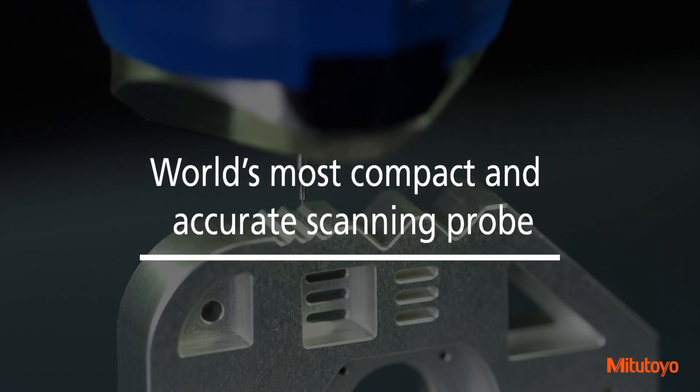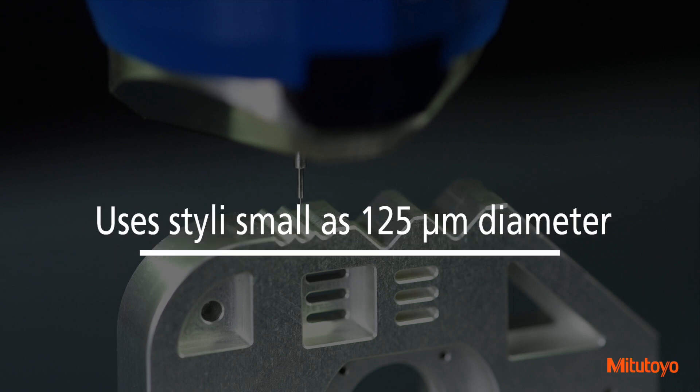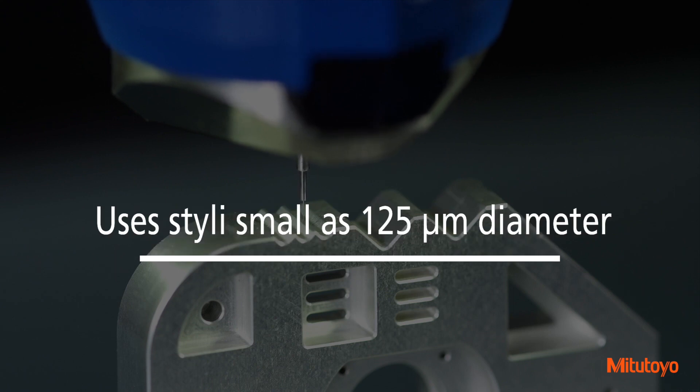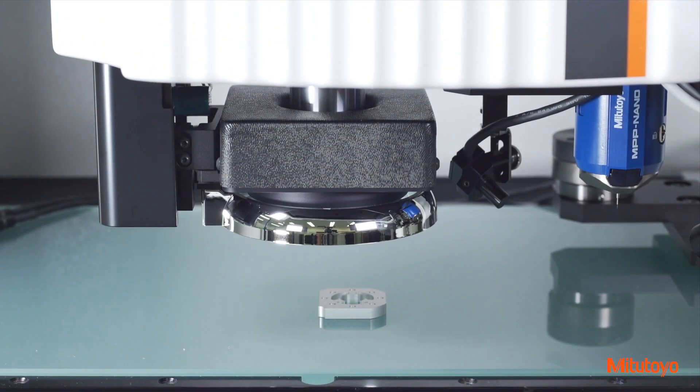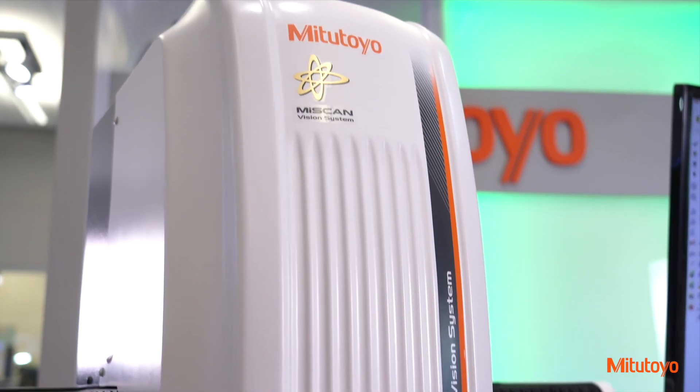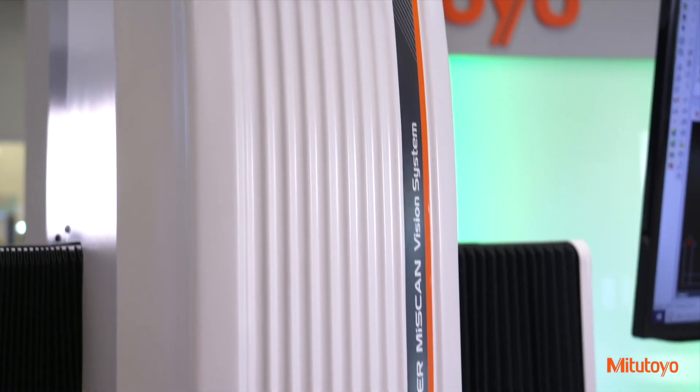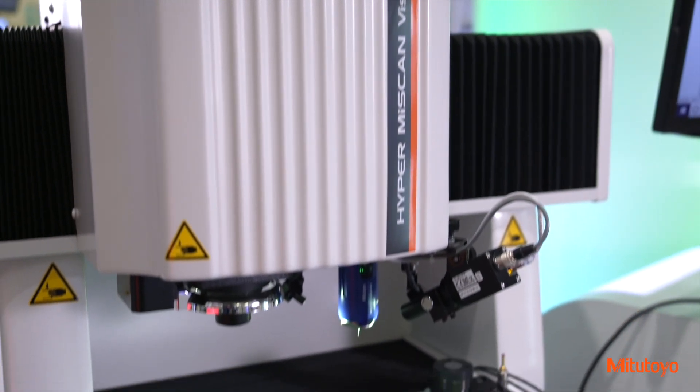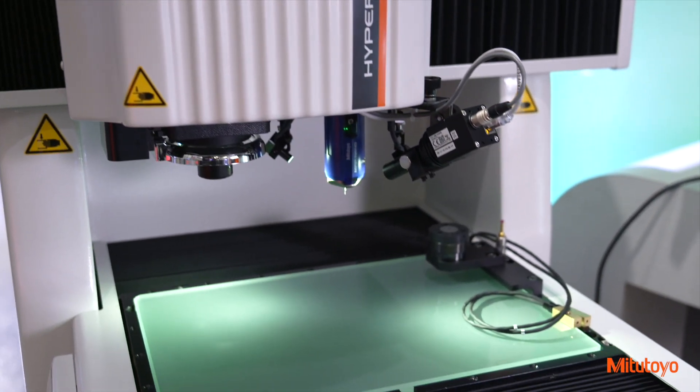The MPP Nanoprobe is the world's most compact and accurate scanning probe, and it can use styli as small as 125 micrometer diameter. An observation camera makes measurement setup easy. The SP25M scanning probe is also supported to measure small and large-sized workpieces and features.